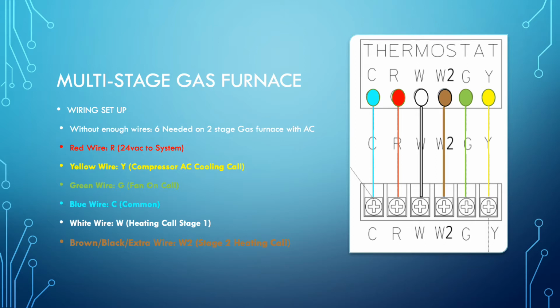Now, depending on what wire is available to you, presuming that you do in fact have those 6 wires, commonly it's going to be brown, or it actually might be black. It doesn't matter what you use, because after the primary red, blue, green, yellow, and white, any other colors can be used as you see fit. So there's no standard past that point. If you have a black wire or a brown wire, in this case I colored it brown, but it's probably going to be black if you just have enough wires to get the job done. If you have 6 wires going to the thermostat, you probably actually have 8. So you're probably going to have a couple of extra wires in there.